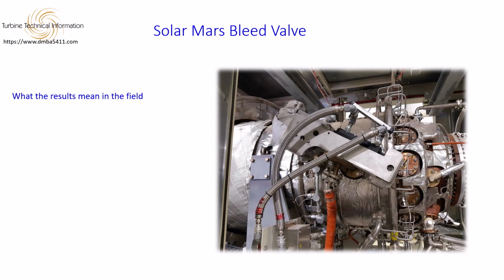What the results mean in the field. So, a quick bleed troubleshooting roundup. Hung start, check for too much bleed. Wrong size bleed. Bad calibration, valve not reaching its scheduled position. Signs of surge during acceleration? Not enough bleed. Position feedback looks correct but behavior is wrong? Closed stop calibration is suspect. And always ask one question. Is the control system configured for the actual hardware installed? Because if the software thinks it's a 4-inch valve, and the casing has a 6-inch, you will chase your tail for days.